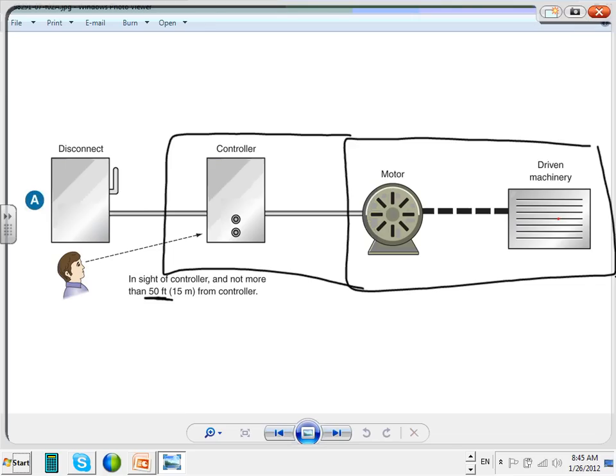Can I dare to write one thing, guys? Most of the time in a commercial building, I would dare to say 90% of the time, you are going to have one disconnect and all the controller, the motor, and the driven machine all in one big box. In a commercial building. Now you go industrial, it's completely different. You can have the motors laid all over and the machines all over and the controllers all over too.